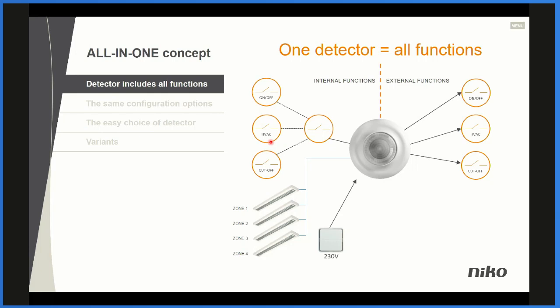But it's not that easy for everybody. If you want to dim the light, you have to press the push button and hold it. Sometimes it's easier for people to have a potentiometer. That means if you like to override it manually, you can just turn the potentiometer clockwise, and then you raise the light level. Or on the opposite, you can turn it anti-clockwise, and then you lower the light level. It's also possible if you like to have some kind of scenarios. You can put in a 230 volt push button along with an interface connected to the DALI bus, and you can program it like you want to.